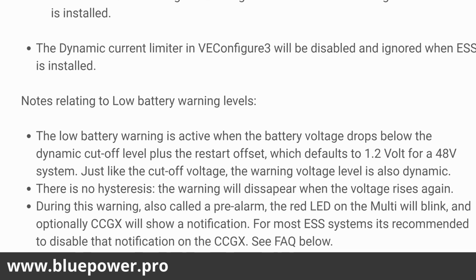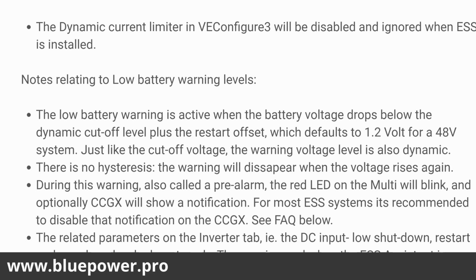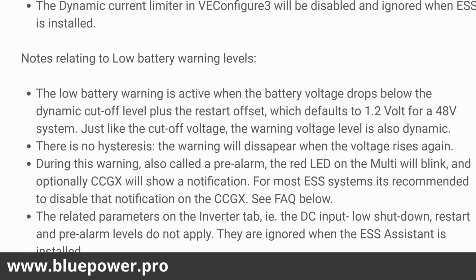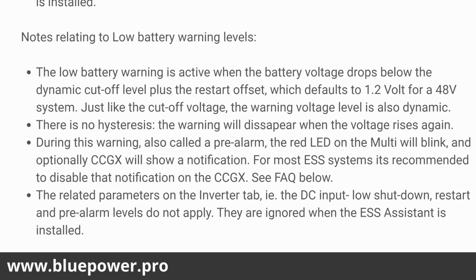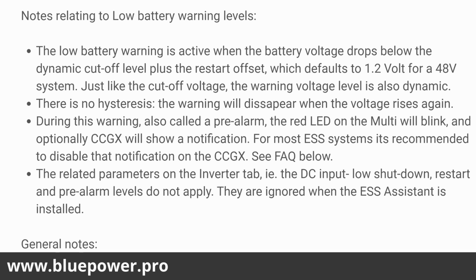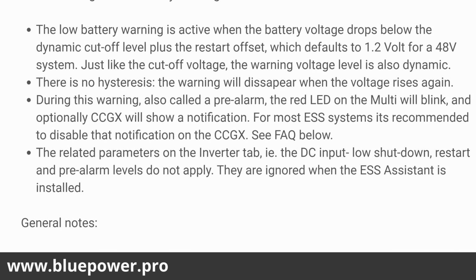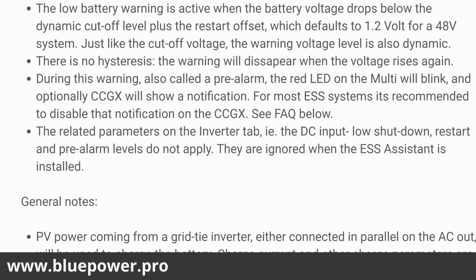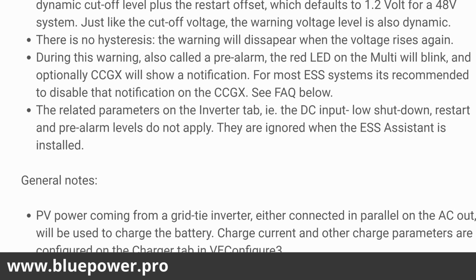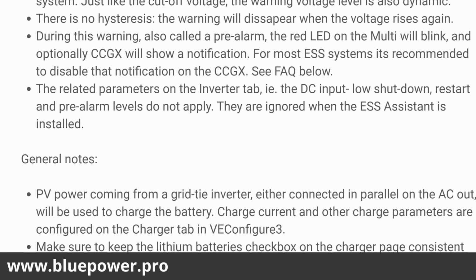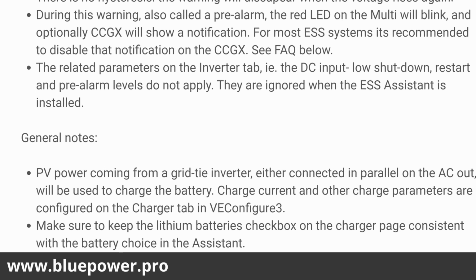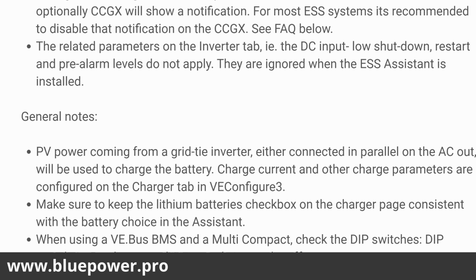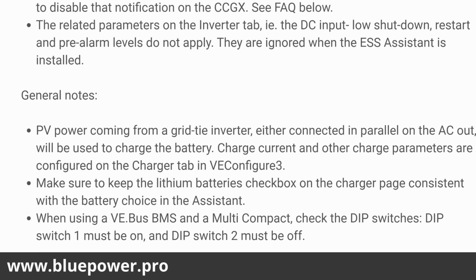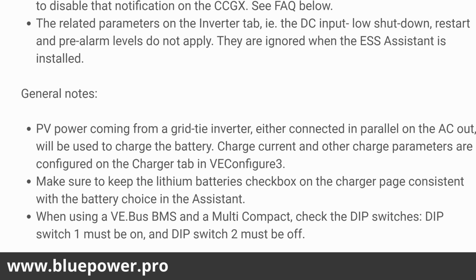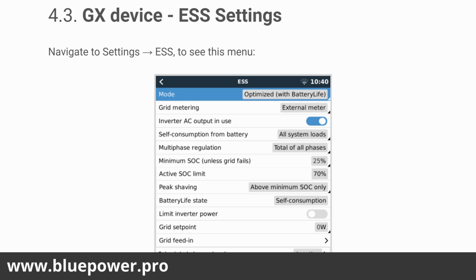So you're going to have to configure some type of grid code onto the inverter to be able to load an ESS Assistant onto the inverter. The ESS Assistant cannot work with the standard grid settings on the inverter, so it is required to set it to the grid code which corresponds to the area. So here's our GX device ESS settings.